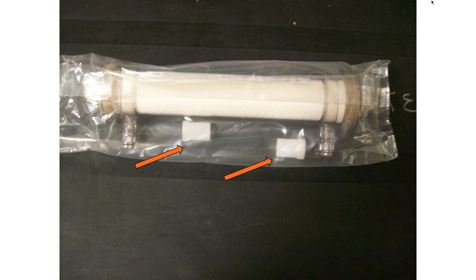And most of the manufacturers, and forgive me for showing one manufacturer's items, because that's what we use in my facility, but all of the dialyzer manufacturers are similar to what this one company does, including the machines. They have their different principles, but all of them use the same methodology and same safety features, some more enhanced than others. But anyway, these caps are intended for a purpose. How many times have you seen staff actually throw those away before they prime? And this one here, if you've not seen what a fiber looks like, it actually looks like that. There's over 10,000 of those fibers in that dialyzer. And it's very, very permeable to fluid water, KUF of 45.